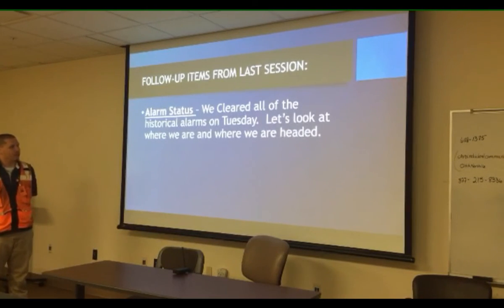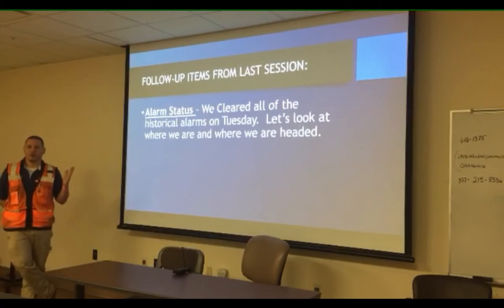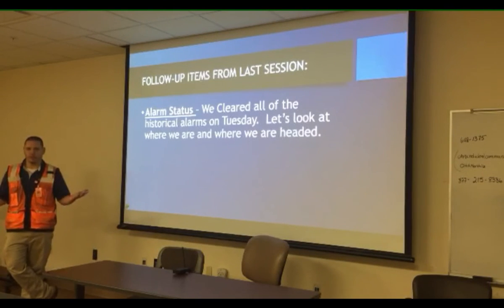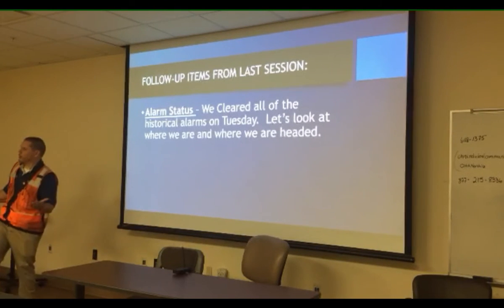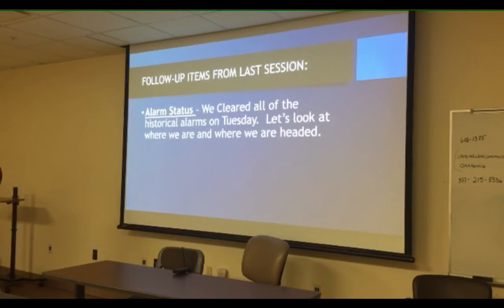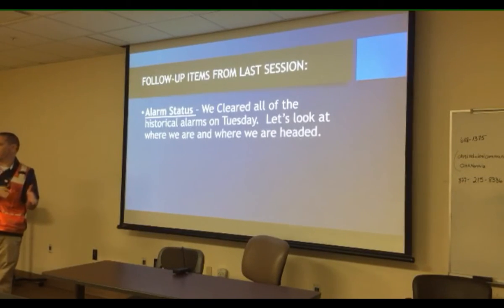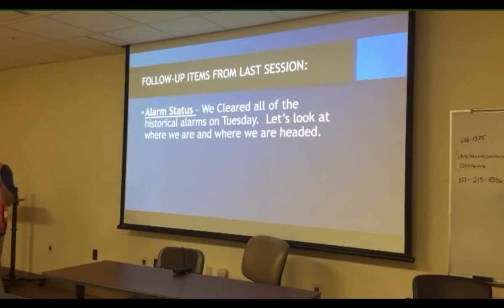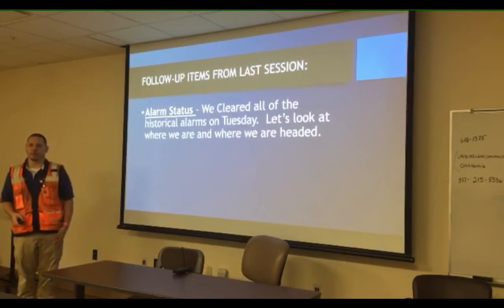And then alarm status - so we cleared everything last Tuesday. We'll pull it up here before we get started, take a look, and talk through what that means. Not all the alarms are cleared, there's some on the system - 14,713. But we want to make sure you understand what those alarms mean and what we're working on, and some of those are just nuisance alarms that we're just going to have to start weeding out and get them down to a reasonable number of alarms that are meaningful. Because that's really what we're gonna do at the end of the day.